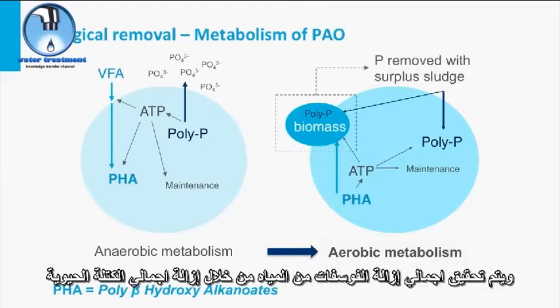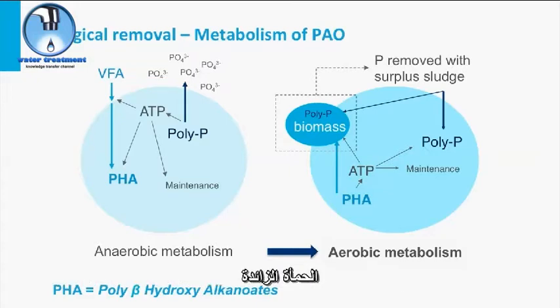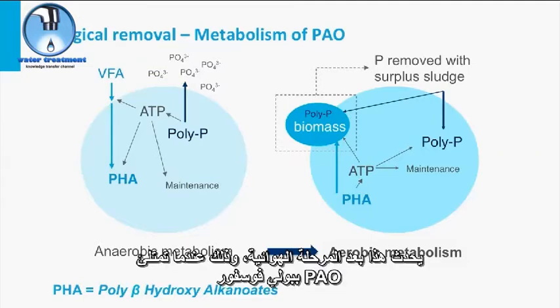Net removal of phosphate from the water is achieved through the removal of the net biomass growth — the waste-activated sludge. This happens after the aerobic phase, when the PAO are filled with polyP.